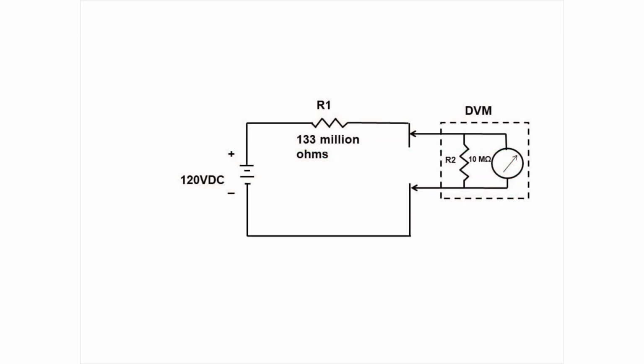Remember the example of the DC voltage divider resistance ratio. In this voltage divider, reducing R2, which here is the effective resistance of the DVM, should cause the phantom voltage to go away or to be reduced to something very tiny. A simple way to do this is to connect something with a small resistance across the DVM. This will cause the equivalent of a DC voltage divider where the voltage across the meter is nearly zero. Let's see how to do this in the real world.